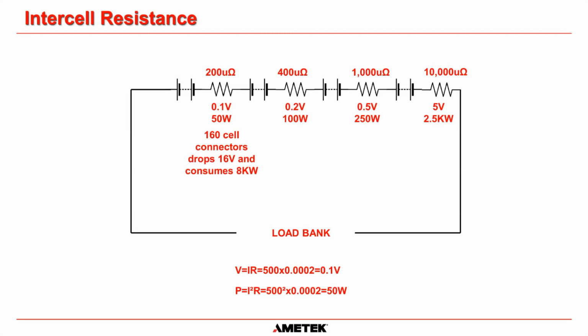Once again, there is no industry standard for what to expect. Every resistance is going to be different depending on how big the strap connection is, its surface area, how long it is. Many things affect it. So once again, to get a baseline, you would have to make sure that the battery is installed correctly, and then get the average reading from all of those connections to get you a good baseline.